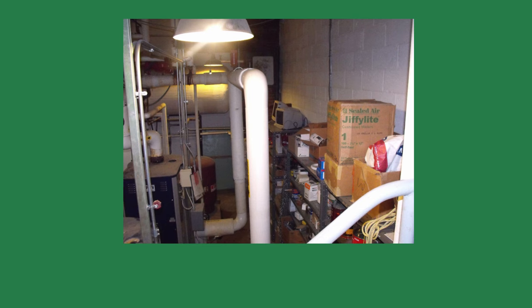When I walked into the new customer's boiler room, the piping swayed back and forth and made a banging sound like someone was hitting the pipe with a hammer. It reminded me of steam hammer, but different. I shut off the boilers, but the banging kept going. I found the pump disconnects and shut them off. The noise and swaying stopped.